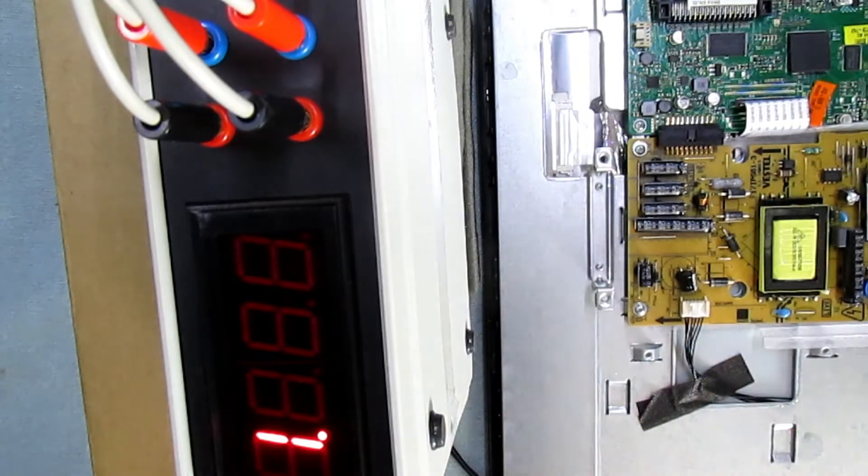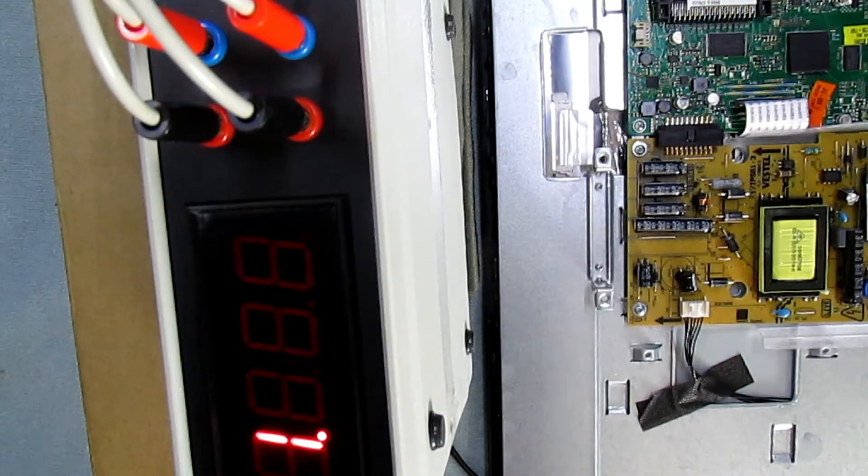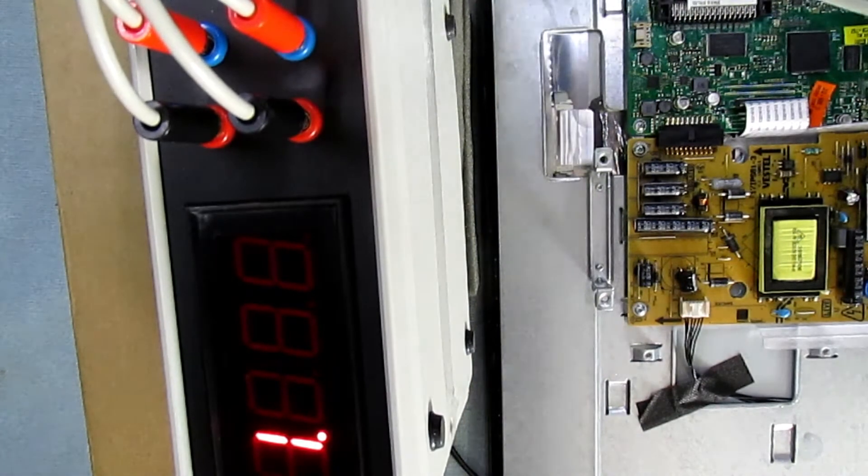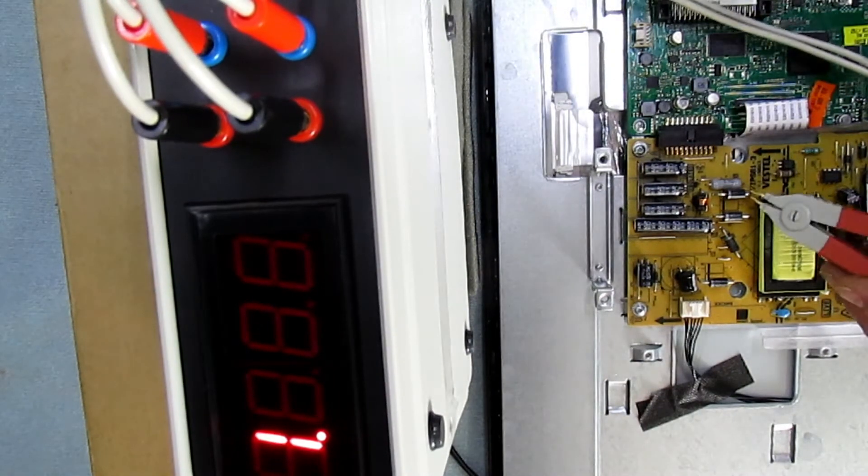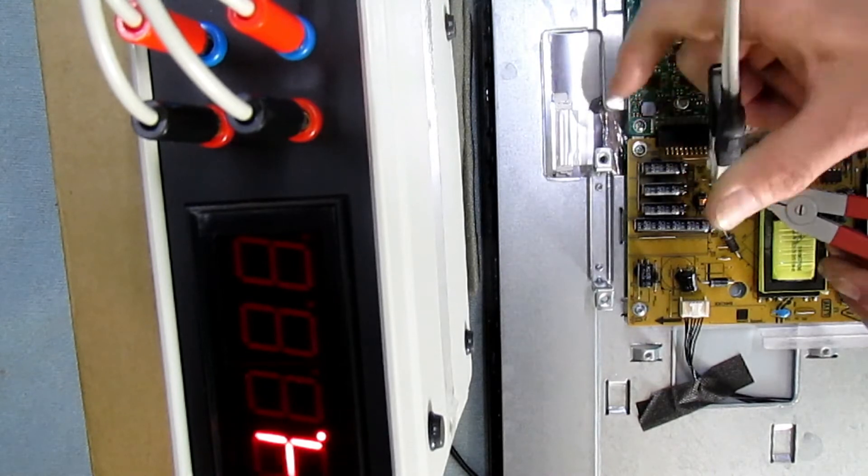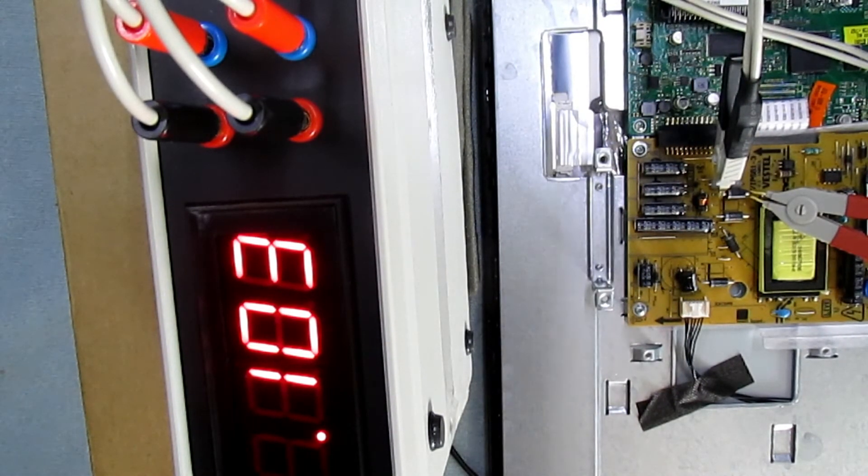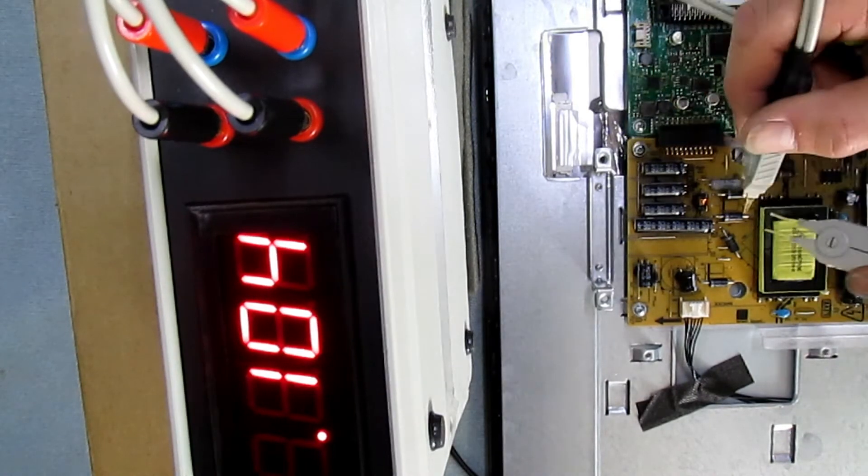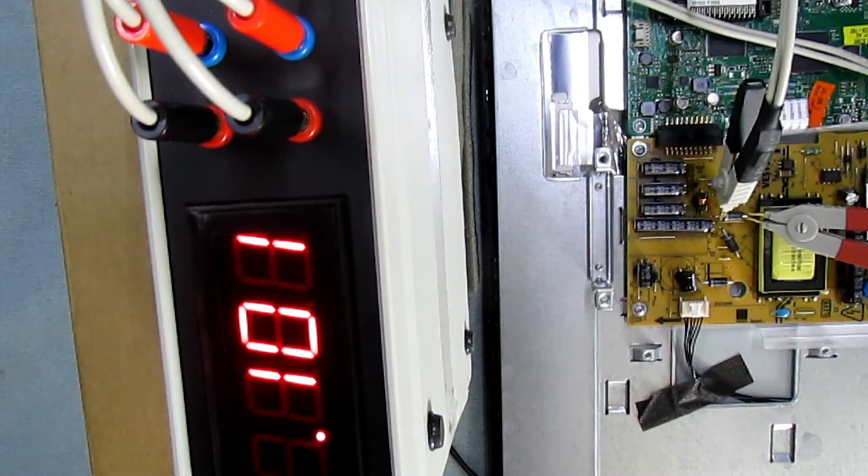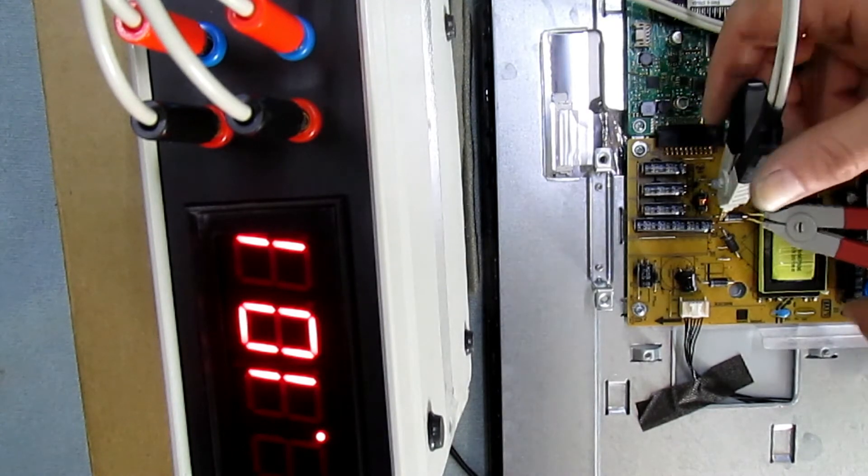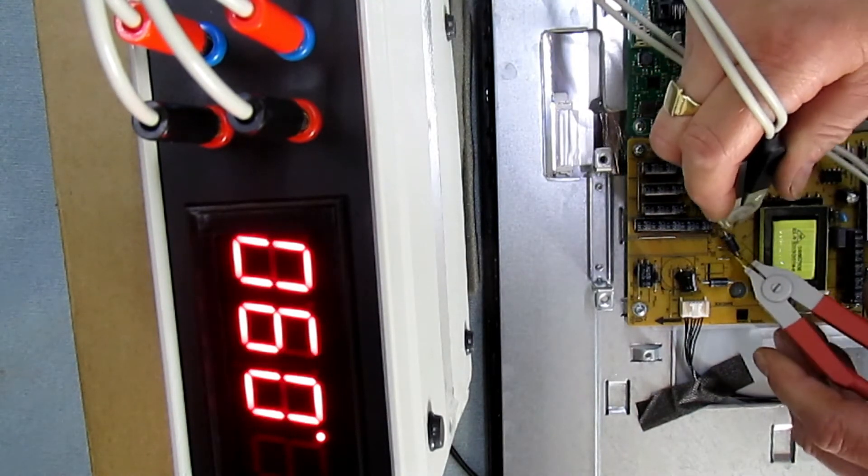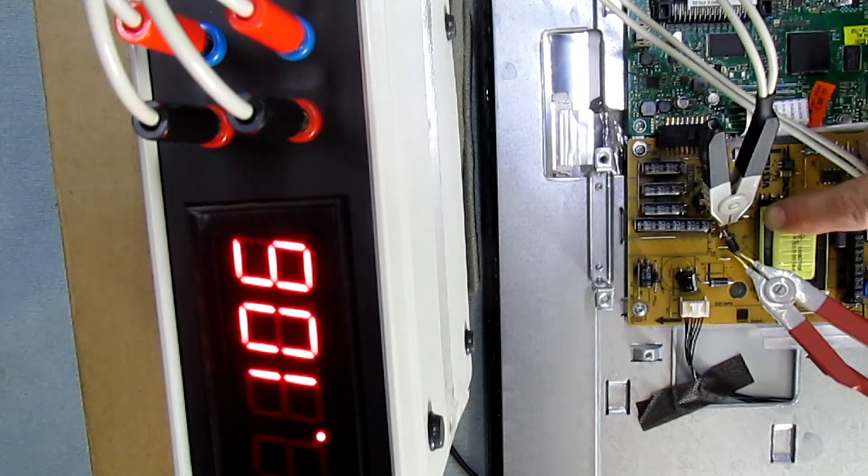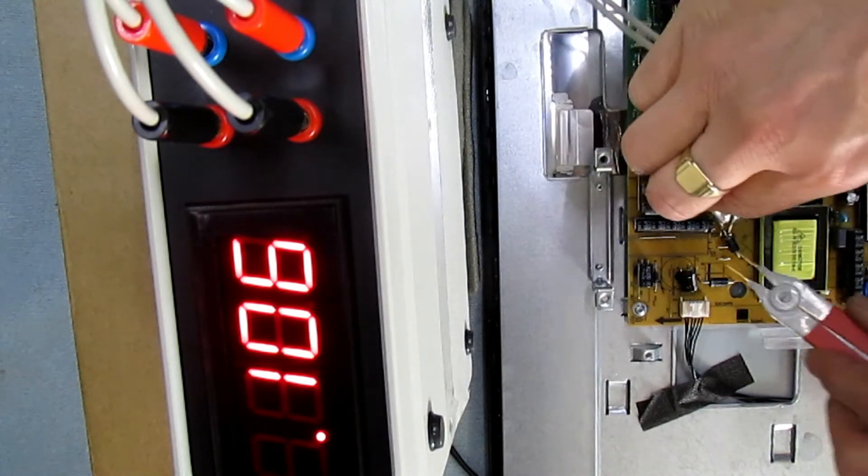So what we'll do is take a reading across that one first. That's 103 milli-ohms. Take a reading across that one, that's 101 milli-ohms. Take a reading across that one, that's 106 milli-ohms. The one with the lowest reading is the center one, 101 milli-ohms.